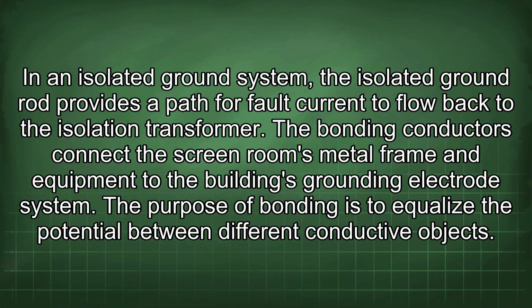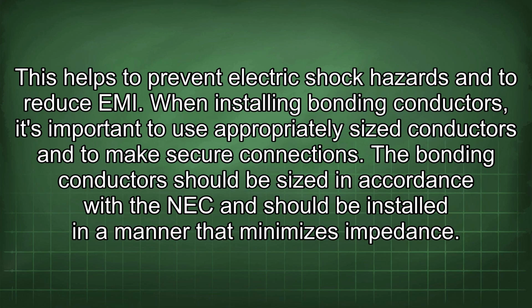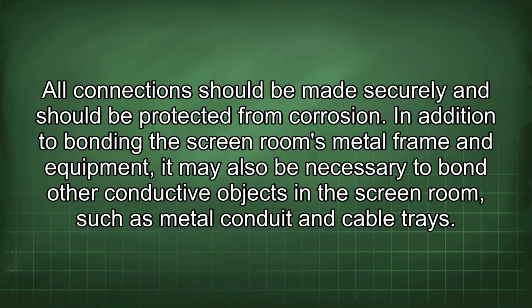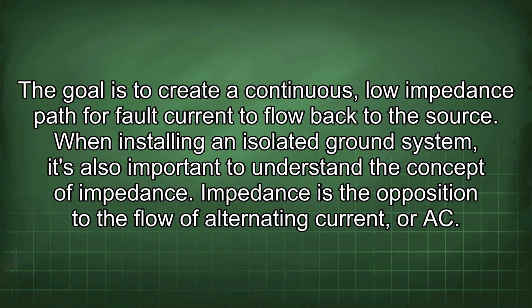The purpose of bonding is to equalize the potential between different conductive objects. This helps to prevent electric shock hazards and to reduce EMI. When installing bonding conductors, it's important to use appropriately sized conductors and to make secure connections. The bonding conductors should be sized in accordance with the NEC and should be installed in a manner that minimizes impedance. All connections should be made securely and should be protected from corrosion. In addition to bonding the screen room's metal frame and equipment, it may also be necessary to bond other conductive objects in the screen room, such as metal conduit and cable trays. The goal is to create a continuous, low impedance path for fault current to flow back to the source.